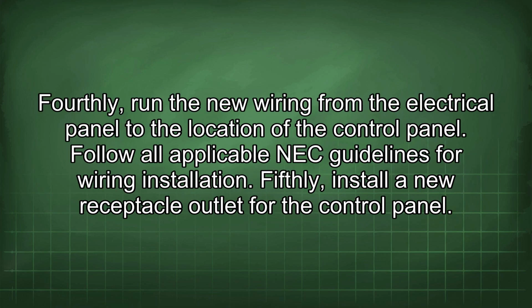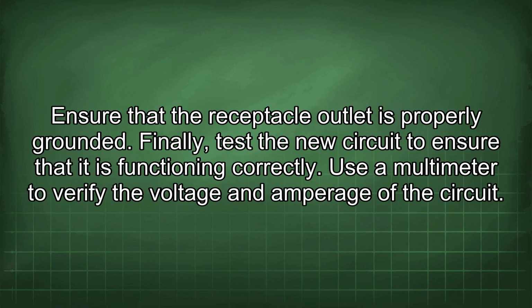Fourthly, run the new wiring from the electrical panel to the location of the control panel. Follow all applicable NEC guidelines for wiring installation. Fifthly, install a new receptacle outlet for the control panel. Ensure that the receptacle outlet is properly grounded. Finally, test the new circuit to ensure that it is functioning correctly. Use a multimeter to verify the voltage and amperage of the circuit.